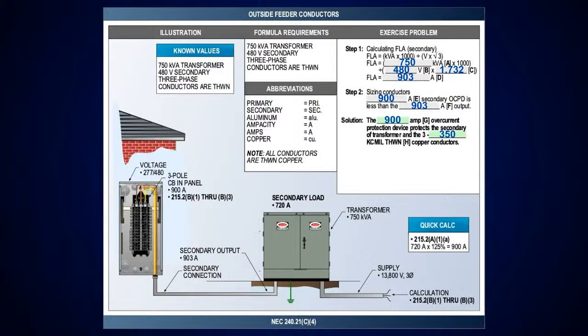So here's one. You'll notice there's no length here we're talking about, and these are the outside feeder conductors. Okay, where I'm going, outside transformer. We even put a new transformer in like you would see outside. We've got a 750 kVA transformer, and you look at that secondary connection. What is it? It's 480 volt, 3-phase, 1.732. That'll give you 831 volts. You divide that into the VA of your transformer, gives you 903 amps.